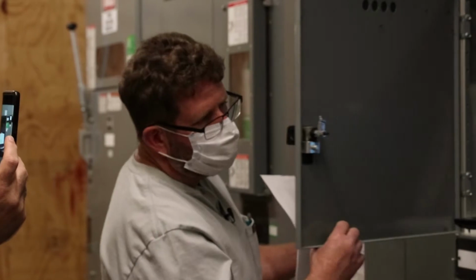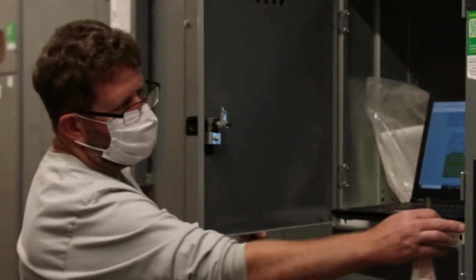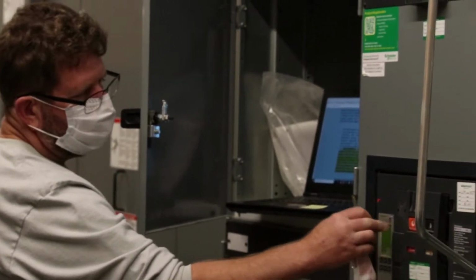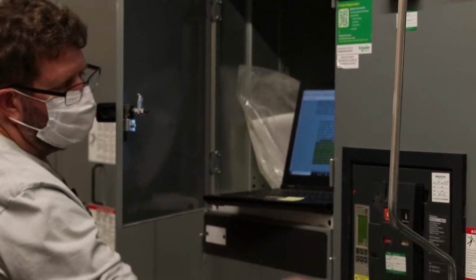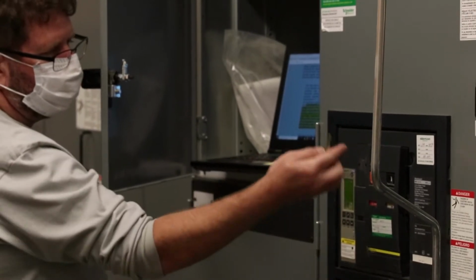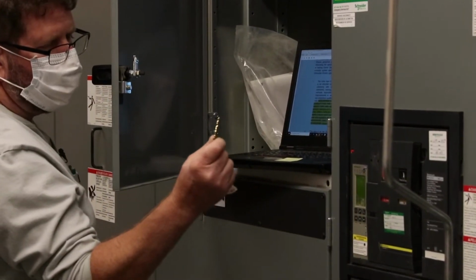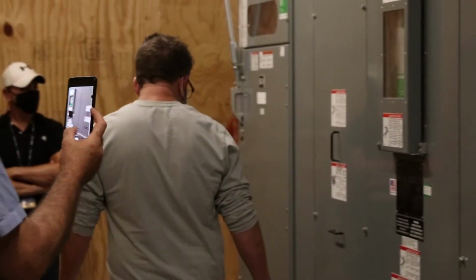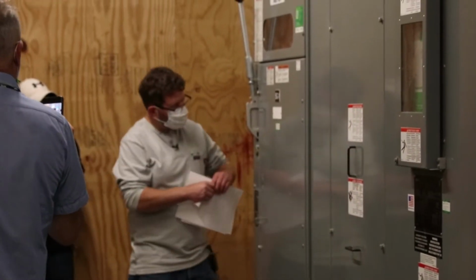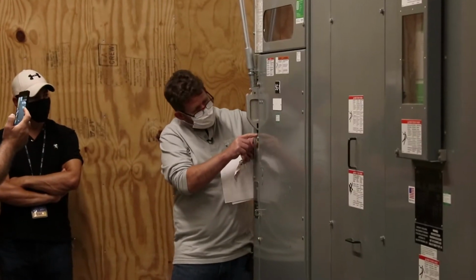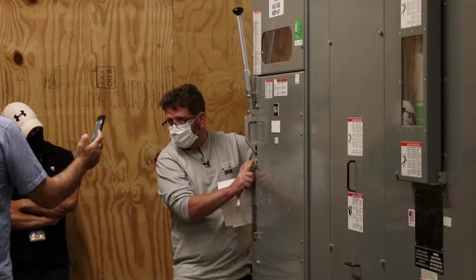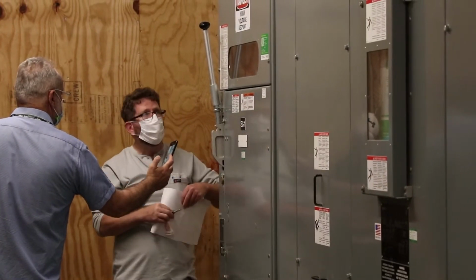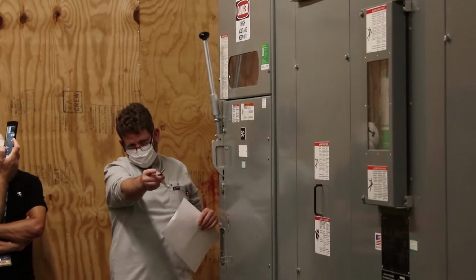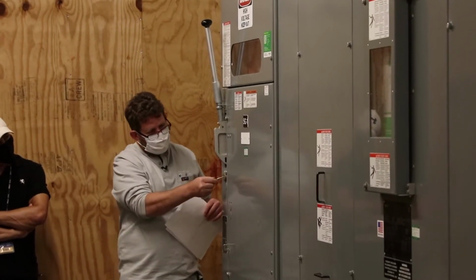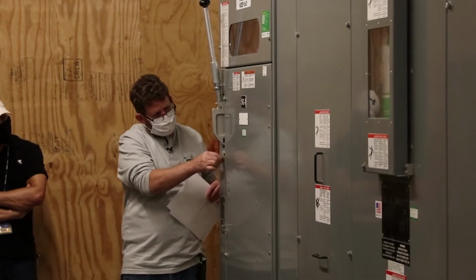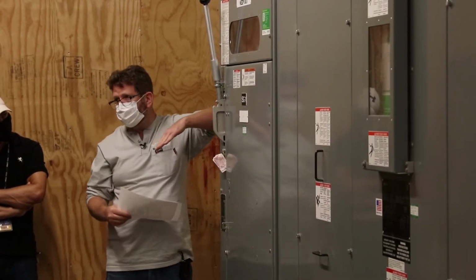But that Kirk lock is built to be installed in here and held in here if the breaker's closed. So to open that switch, you would have to come down here, open this breaker, lock it open, and bring the key down here to the switch. If you notice right here, without the key in the cylinder, the shaft is going up into the operator. That's going to prevent this switch from being operated right now. So with the breaker open, locked open, release the key, you'd be able to come down here, put it in the cylinder, retract the shaft, and then you could open this switch.